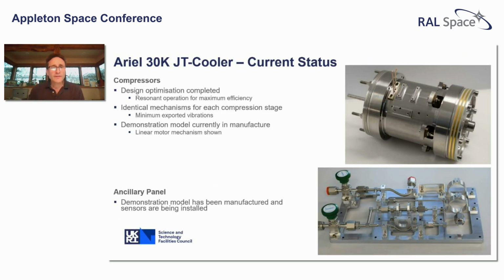This is the current status of this cooler. For the compressors, we've optimized the design. It's important that you operate the compressors at resonance to maximize the efficiency of the cooler.